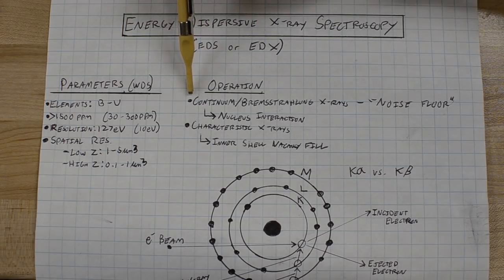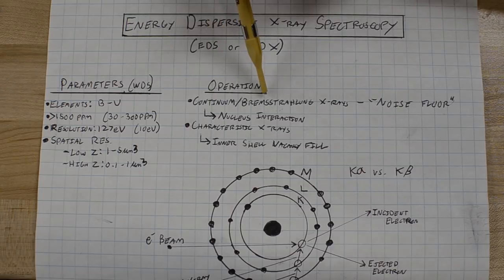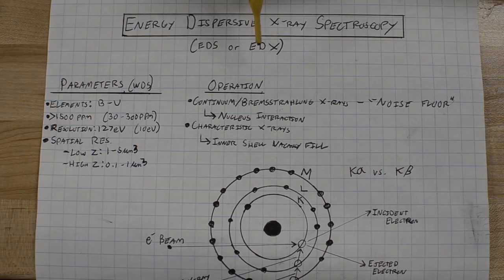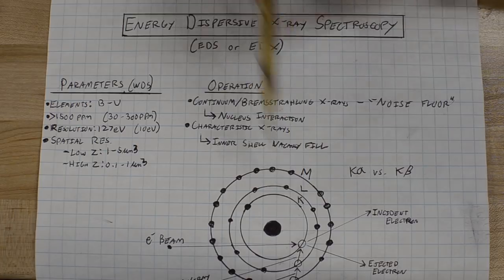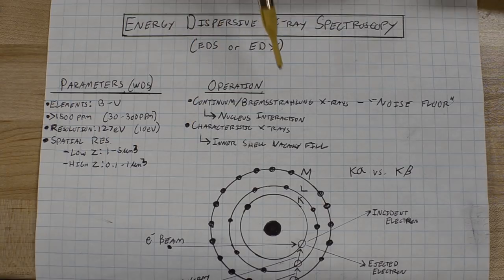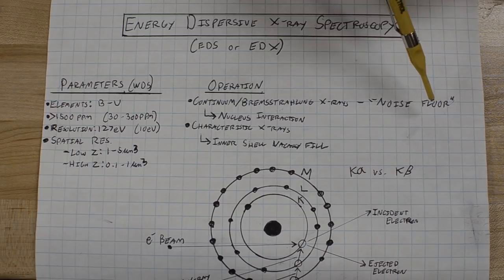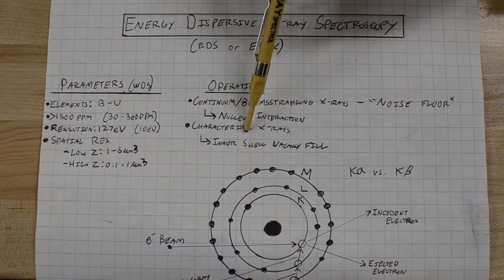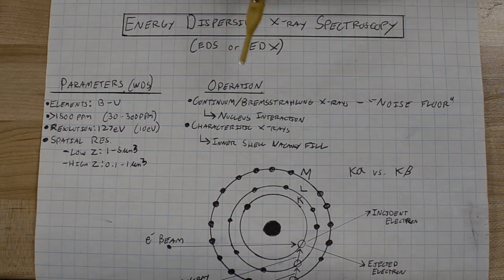The first is basically a nuisance to what we're trying to do here. This is continuum X-ray generation. The German word for it is Bremsstrahlung. These X-rays are not characteristic of the atom they came from. There's no way of differentiating continuum X-rays from a cobalt atom from an iron atom. This basically makes up the noise floor.